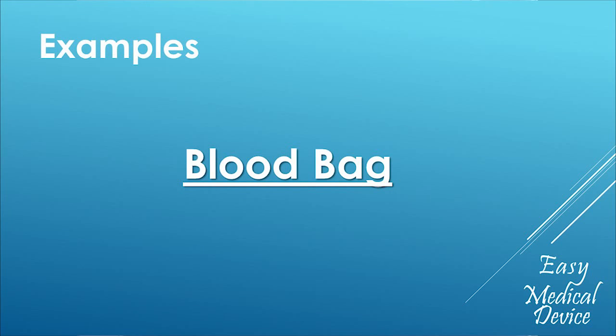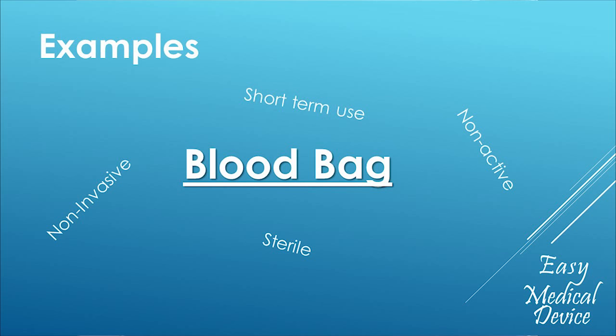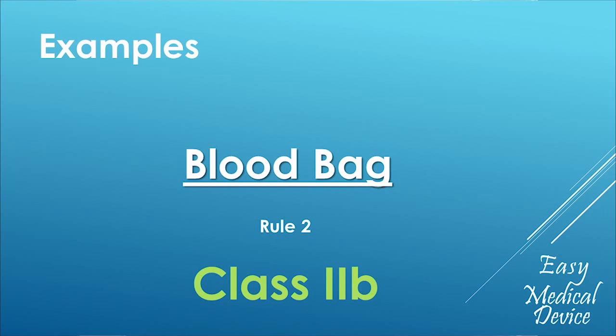Let's increase the difficulty a bit — let's go for a blood bag. The answer is Rule 2, Class 2b. This one was also an easy one; the text of Rule 2 says directly that a blood bag is Class 2b.